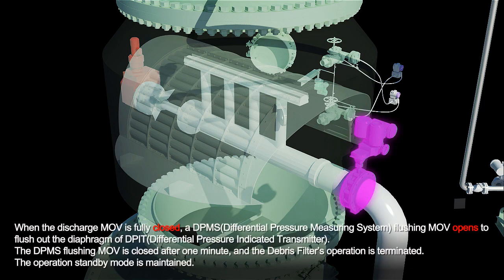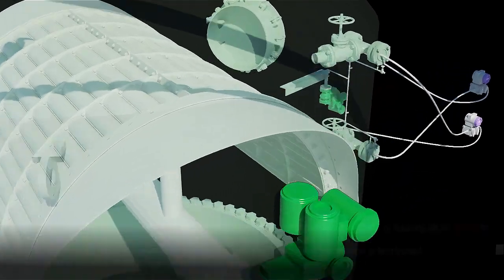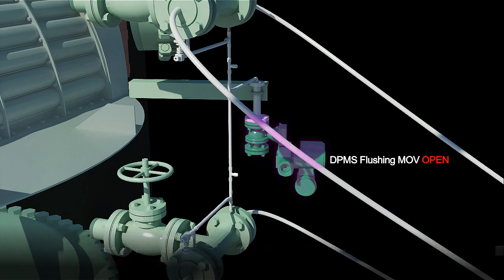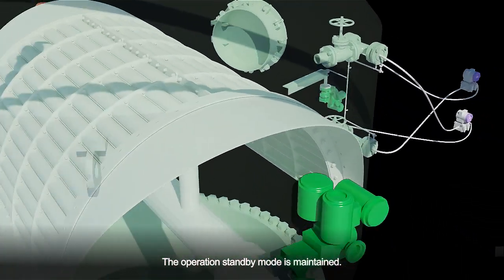When the discharge MOV is fully closed, a DP-MS flushing MOV opens to flush out the diaphragm of DPIT. The DP-MS flushing MOV is closed after one minute and the debris filter's operation is terminated. The operation standby mode is maintained.